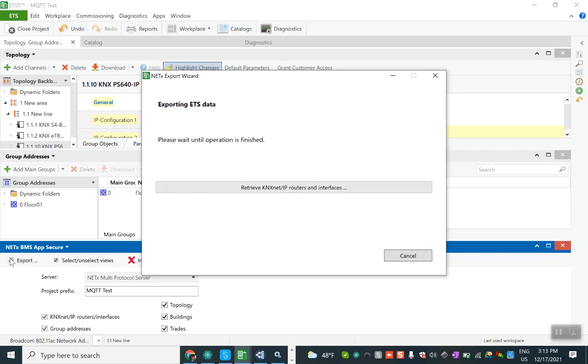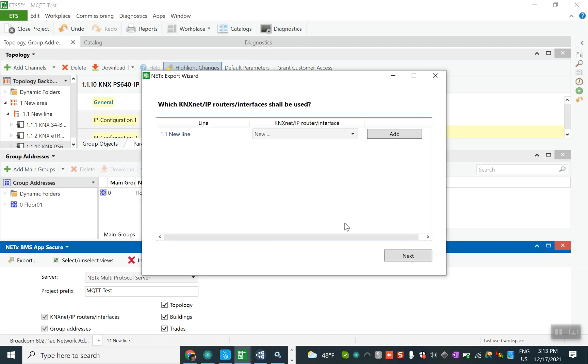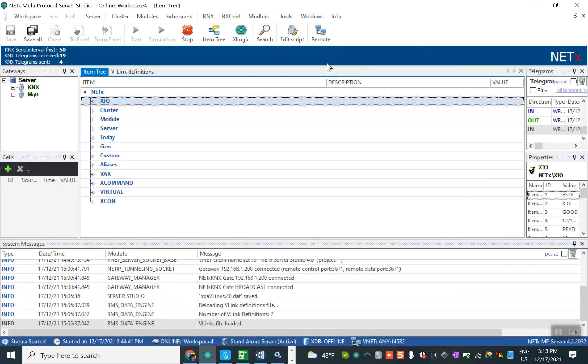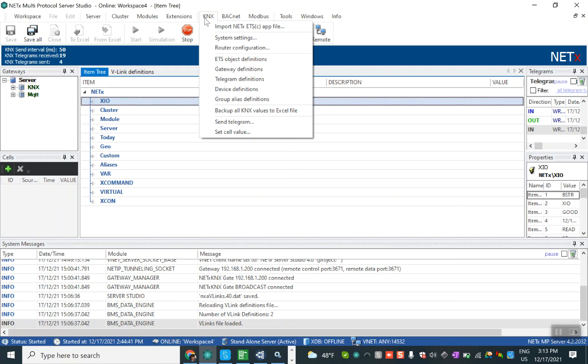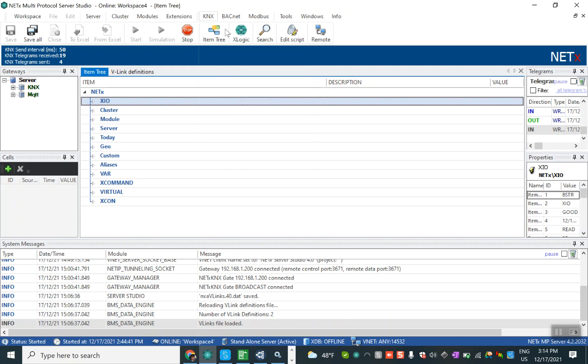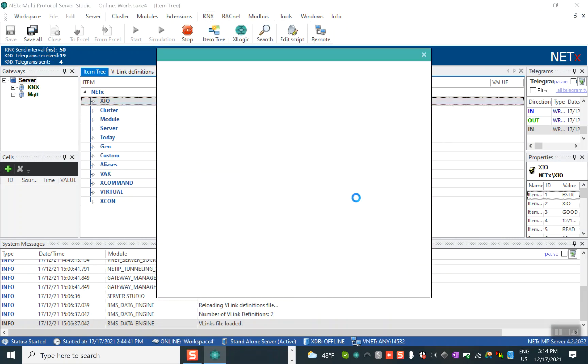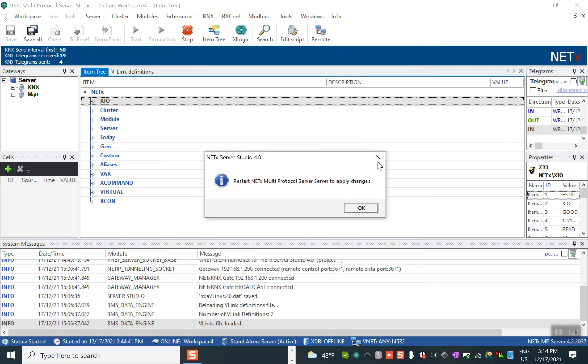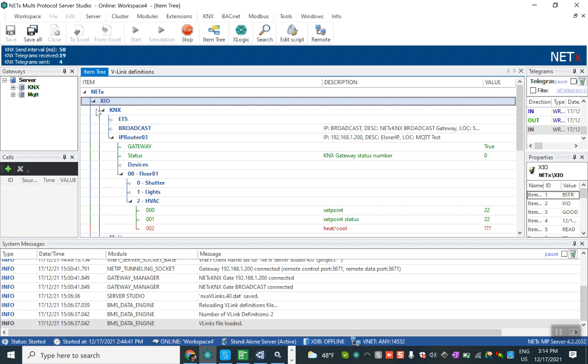After we export, we should go to the NetX automation software. From the KNX part in the main menu we can import the exported file from ETS based on NetX app. I select it and replace it. After we do this, the KNX will be connected so all of the project of KNX is coming here. We can see the gateway is true so we are connected to the KNX system.